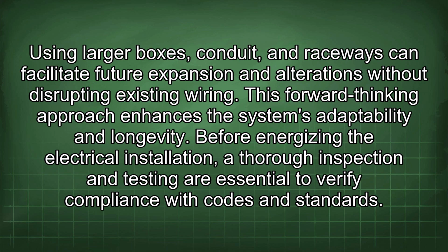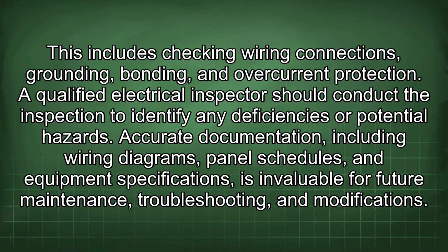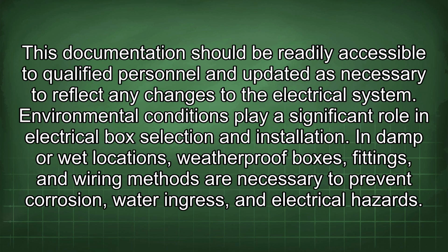Before energizing the electrical installation, a thorough inspection and testing are essential to verify compliance with codes and standards. This includes checking wiring connections, grounding, bonding, and overcurrent protection. A qualified electrical inspector should conduct the inspection to identify any deficiencies or potential hazards. Accurate documentation, including wiring diagrams, panel schedules, and equipment specifications, is invaluable for future maintenance, troubleshooting, and modifications. This documentation should be readily accessible to qualified personnel and updated as necessary to reflect any changes to the electrical system.